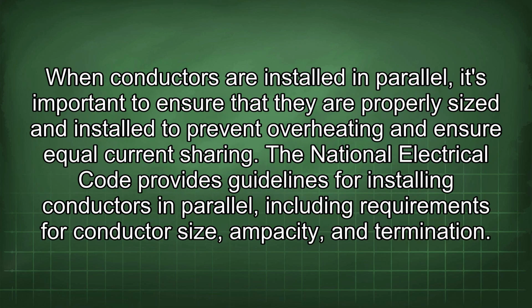When conductors are installed in parallel, it's important to ensure that they are properly sized and installed to prevent overheating and ensure equal current sharing. The National Electrical Code provides guidelines for installing conductors in parallel, including requirements for conductor size, ampacity, and termination.